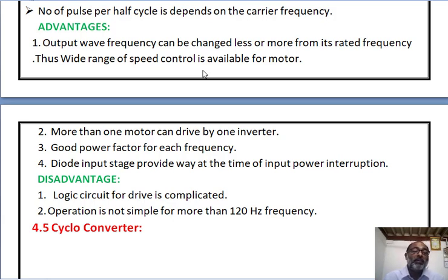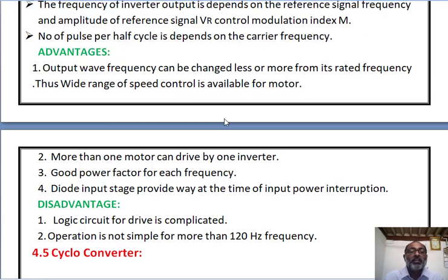Now the power factor is good for each frequency, and the diode input stage provides a ride-through at the time of input power interruption. Disadvantages: the logic circuit for the drive is very complicated. Now operation is not simple for frequencies of more than 120 Hz.